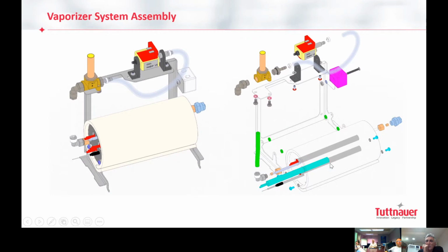This is when we speak about the vaporizer, see how it looks like. It's a very simple system. There is a solenoid valve and the Ulka pump, the water pump, which is providing from here to here. Here it goes into a coil around, and this coil is touching, surrounded by the three heaters. Okay? Right. And those three heaters are just heating up the water, the pulses of water that are coming from here and coming out from here to the chamber.